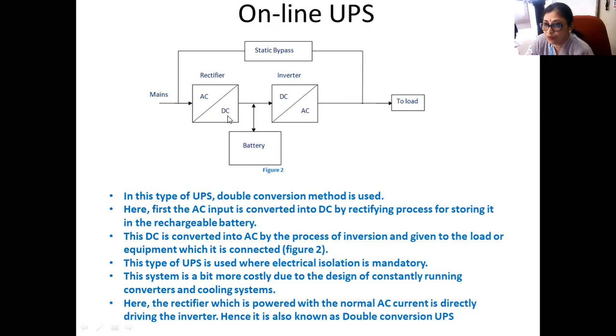But this type of system is costly compared to the offline system, because as the battery is continuously on, it will require cooling systems, and therefore this is the costly one. Here, continuous power is available, and double conversion is done every time - AC to DC and again back to AC.